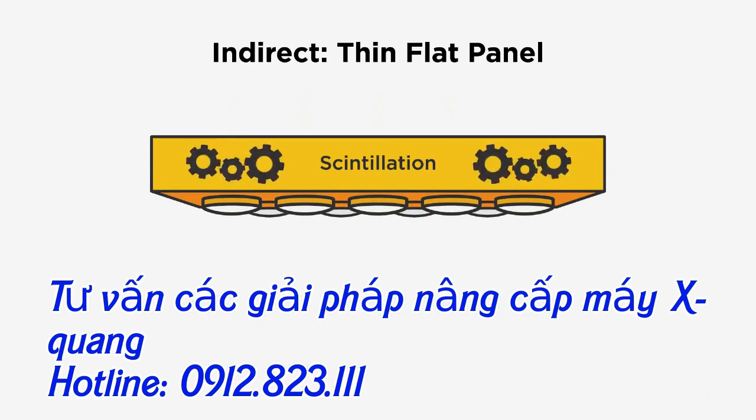The top scintillation layer, or light layer, is where the incoming incident X-ray photons are converted into light photons. A scintillation is nothing more than a burst of light, which is why this layer is called the scintillation layer. Each photon that strikes the scintillation layer creates a small burst of light energy.